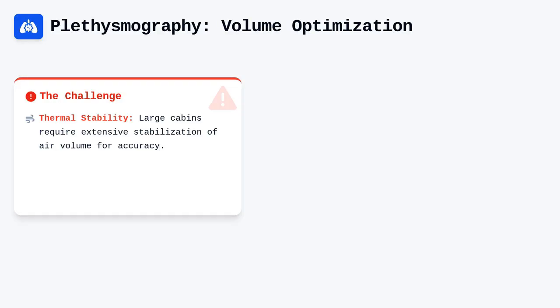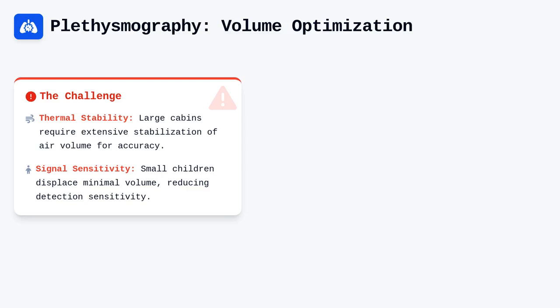Plethysmography presents its own distinct set of challenges, specifically regarding the physical volume of the testing chamber. A large plethysmograph cabin contains a substantial amount of air that must be thermally stabilized before accurate thoracic gas volume measurements can be reliably gathered. When testing a small child, the relative displacement of body volume is minor compared to the total cabin volume, which can make the signal detection less sensitive.